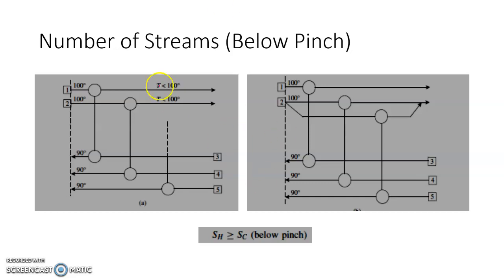If we do not satisfy this condition below pinch, the temperature difference will not remain as required and ΔT minimum cannot be maintained. So we need to split the hot stream below pinch in that case. This is the first condition required for heat exchanger networking: above pinch, hot streams must be less than or equal to cold streams; below pinch, hot streams must be greater than or equal to cold streams. Other conditions will be discussed in the next video.